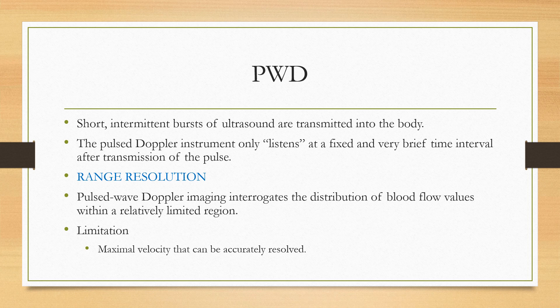We study the ultrasound waves which reach a particular sampling point. We can select the sampling point in the 2D image, and the transducer will receive reflected sound waves from the RBCs from that sampled point only. Even though RBCs between the transducer and the sampling point also absorb and reflect ultrasound waves, the transducer only listens to reflected waves from that particular sampling area at a fixed and very brief time interval after transmission of the pulse. This is the property of range resolution — a key characteristic of Pulse Wave Doppler.